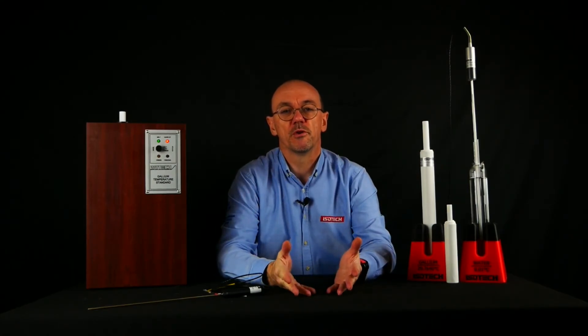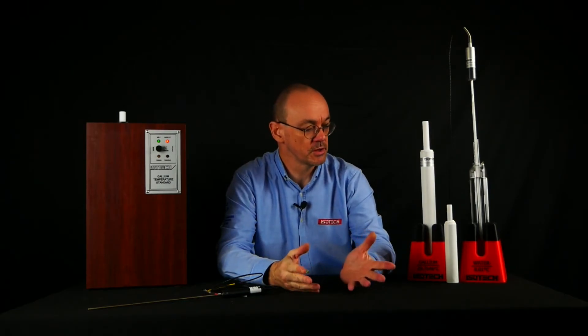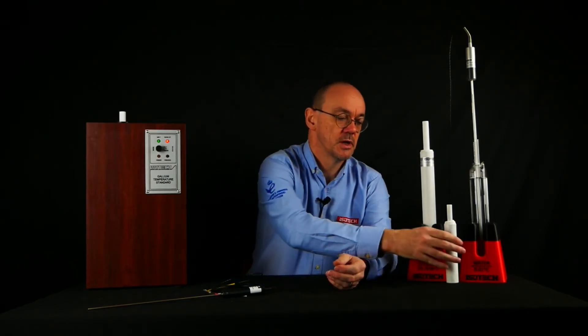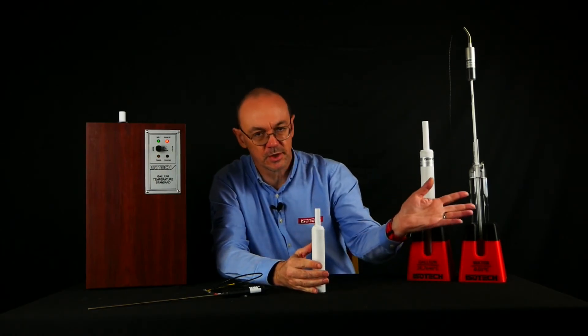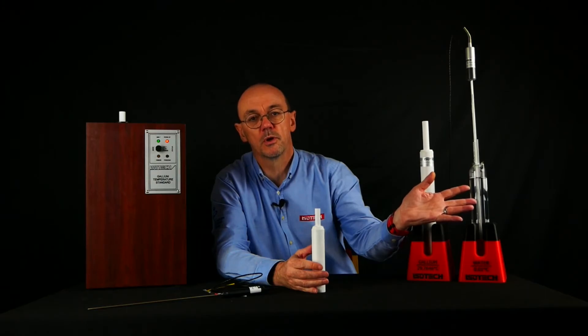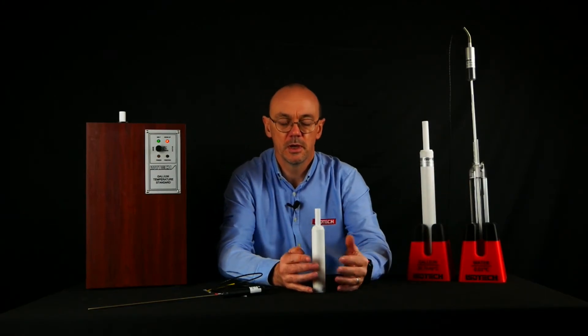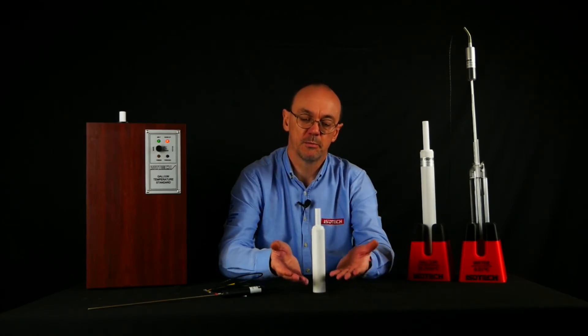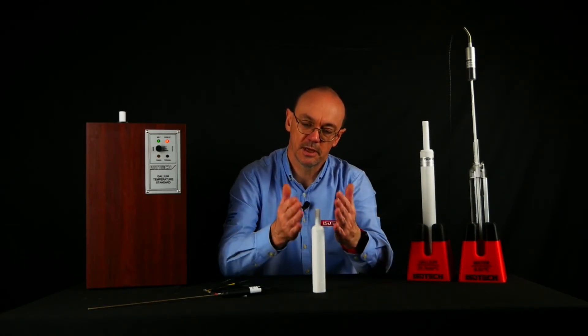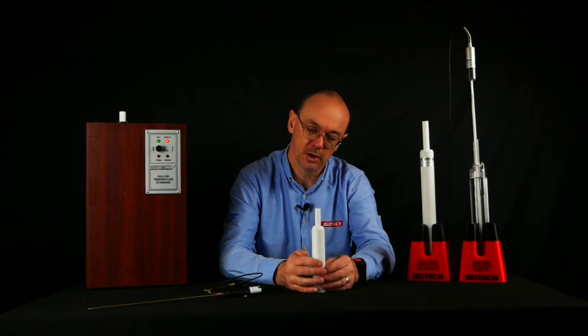Just a couple of final thoughts relating to gallium cells. They're relatively robust, less fragile than certainly the quartz or the borosilicate water triple point cells. They're best stored upright. So if the environment gets warm, the metal will melt and it will be in a known state.